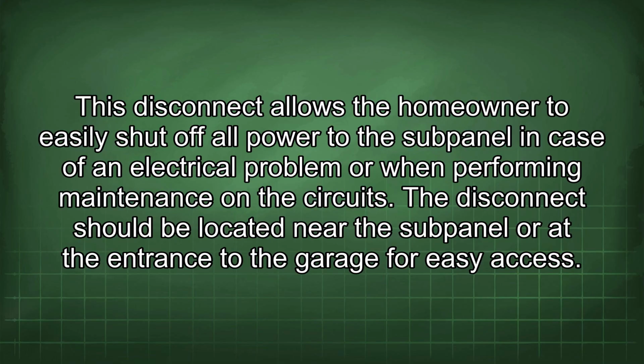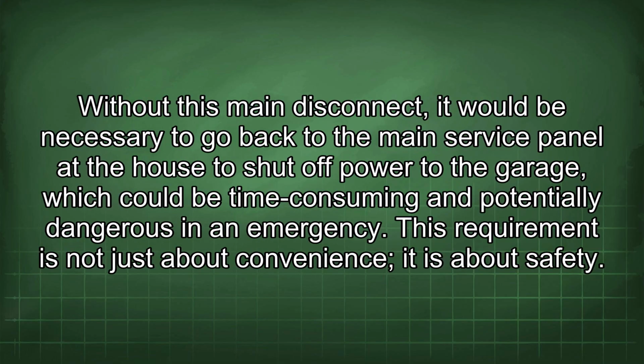The disconnect should be located near the subpanel or at the entrance to the garage for easy access. Without this main disconnect, it would be necessary to go back to the main service panel at the house to shut off power to the garage, which could be time-consuming and potentially dangerous in an emergency. This requirement is not just about convenience, it is about safety.